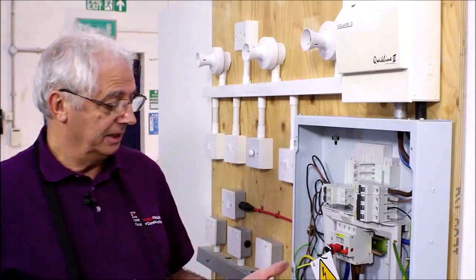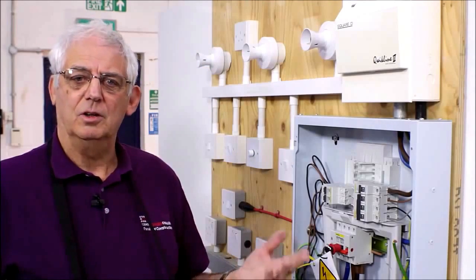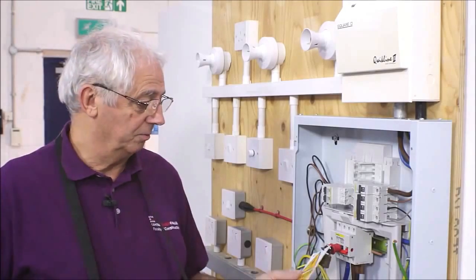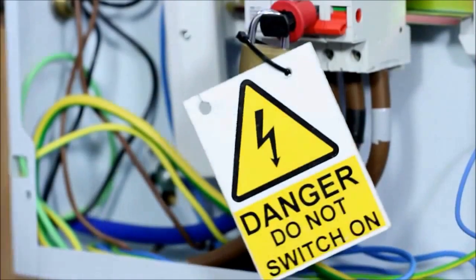We're going to carry out a test now to confirm the integrity of a protective bonding conductor. Obviously this is a dead test and we're going to have to disconnect the bonding to carry out the test properly. So first thing I need to do is isolate the installation, lock it off and make sure I've put the proper labels and locks on so that it's entirely safe. I then need to disconnect the bonding conductor, which I'm going to test.